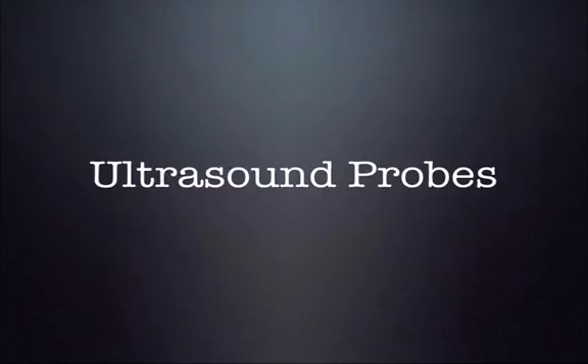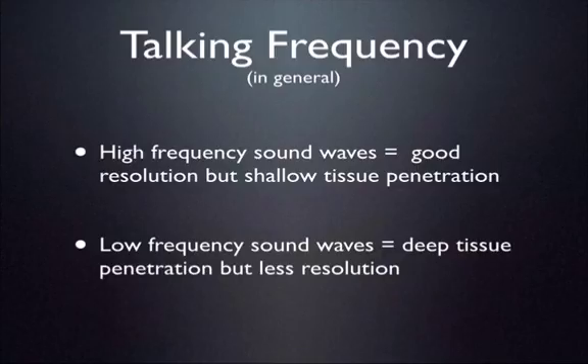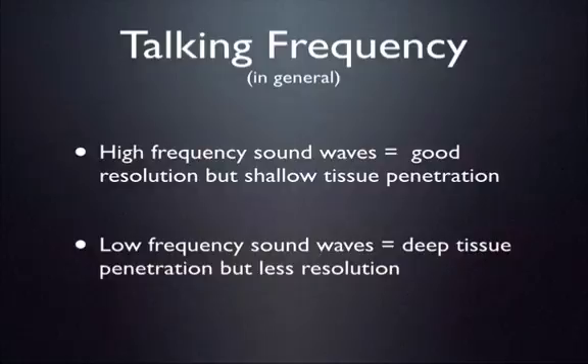Now let's transition and talk about ultrasound probes. There are numerous probes to select from, and the key difference between them is frequency. High frequency sound waves generally equate to good resolution but shallow tissue penetration. Low frequency sound waves generally equate to deep tissue penetration but less resolution.